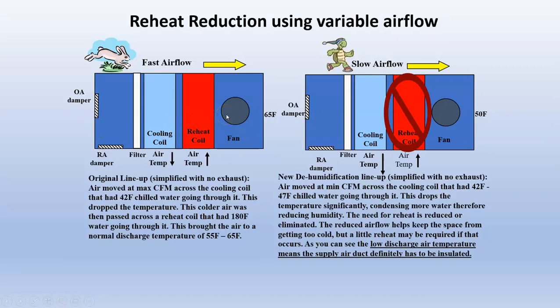Now, another way to think about that is this is a new dehumidification lineup. Basically, I'm going to slow that airflow down. I'm going to put a VFD on it controlled by the BAS, slow the airflow way down, right? Cooling temps, still going to drop out, but my reheat coil, I'm going to get rid of it. Or almost, sometimes I can get rid of it or get close to it. So I'm going to drop that humidity out on this super slow coil here, super slow airflow across this coil. It's going to wring the water out. The only catch is notice the difference in the discharge air temps.